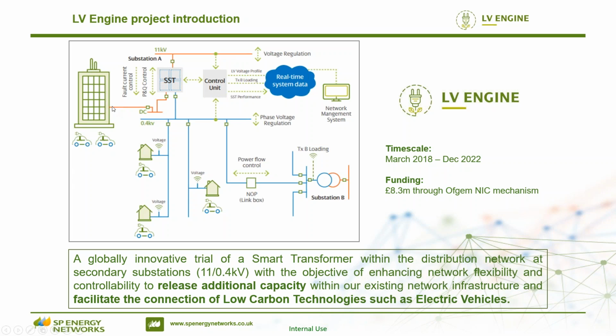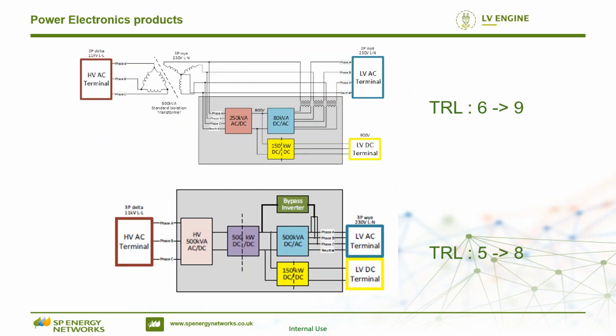LVDC provision is another aspect of our project, basically. So you can see it's quite a move from what we have at the moment as a passive secondary substation to something very, very active. So there are two main products we're going to have in LVEngine. One is a power electronic unit added to the existing conventional transformer. Obviously there is going to be a bit of change, but it's going to be connected through a cable to the conventional transformer. It's a UPFC topology, which by injecting voltage to the main supply from the secondary side of the transformer, and manipulating the voltage and phase, can provide the control we require.